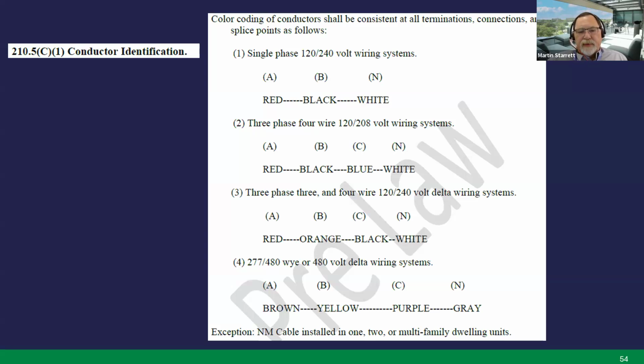Also, it alleviates some required labeling for things like panels and transformers. According to the National Electric Code, you have to label what color you're using on each phase on a lot of electrical equipment. Well, we're telling you what to use, so it keeps you from having to do a lot of that labeling. We've had some form of color coding since about the 1950 electrical ordinance, so we didn't see any sense in removing it, but in 2023 we did help out with the continuous color all the way through the length. And then we also added an exception for NM cable in one- or two-family or multifamily dwelling units, which helped a lot of electricians. Next slide.